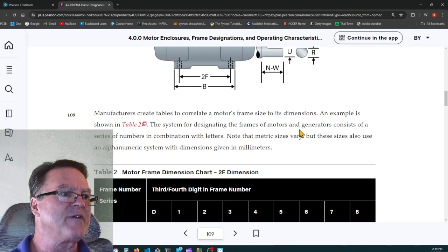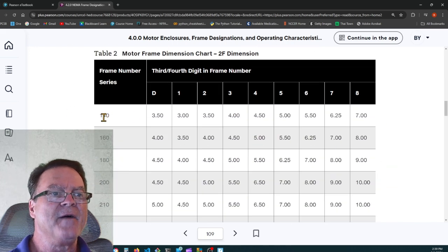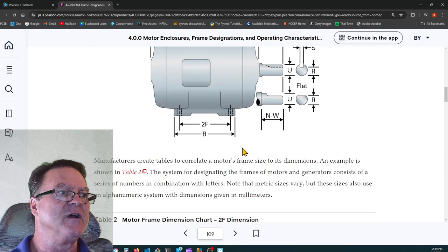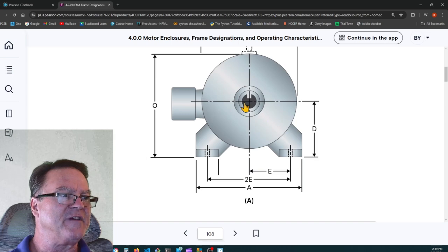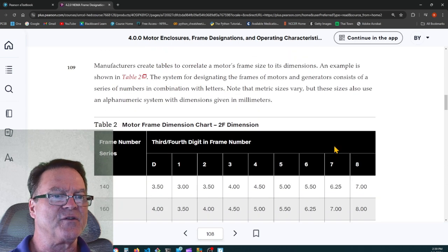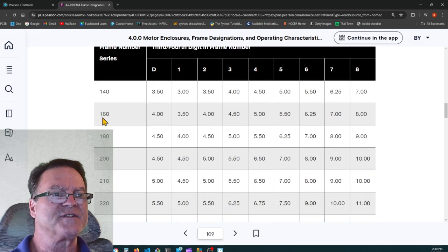The system for designating the frames of motors and generators consists of a series of numbers in combination with letters. So the first two or first three digits give you, what was it, eighths of an inch. So if this is, oh, it's a quarter of an inch, excuse me. So 16 quarters of an inch, it's 4 inches, the D dimension. Remember that D dimension being from the bottom of the feet to the center line of the shaft. So the first two digits is in fourths of an inch, quarters of an inch. So 16 quarters of an inch is 4 inches, and 20 quarters of an inch.